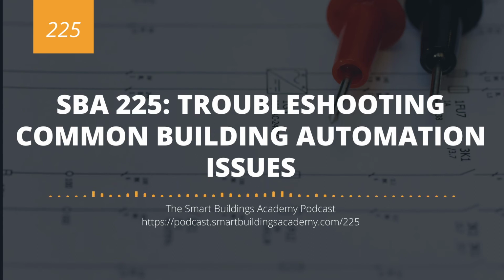You're saying my desired outcome is to command the actual set point. My actual outcome is I can't command the set point. What is the difference? Well, here's the point. And this is where you have to have an understanding of BACnet and understand that AIs do not have a priority array and thus are not commandable or writable.